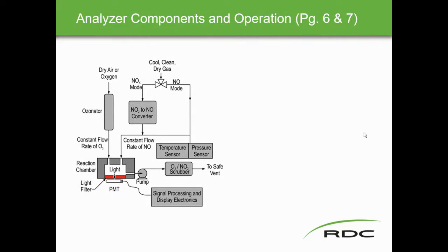Looking at the analyzer components in operation: dry air or oxygen is fed into an ozonator, which converts O2 into O3 (ozone). This is necessary because the core chemical reaction requires ozone and nitric oxide together to produce NO2, oxygen, and emitted light.